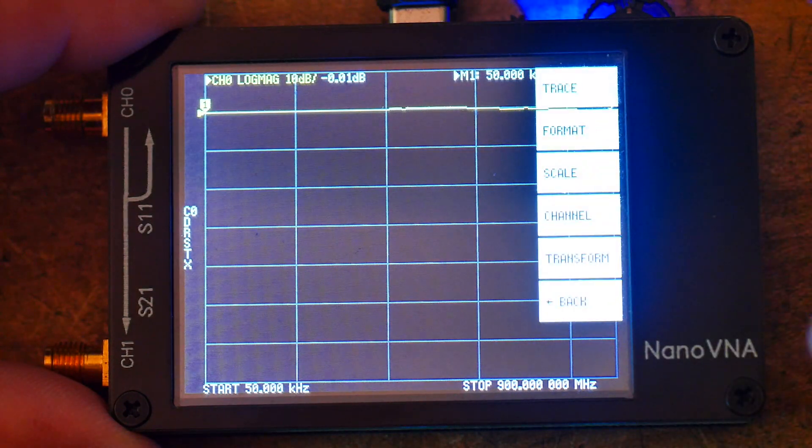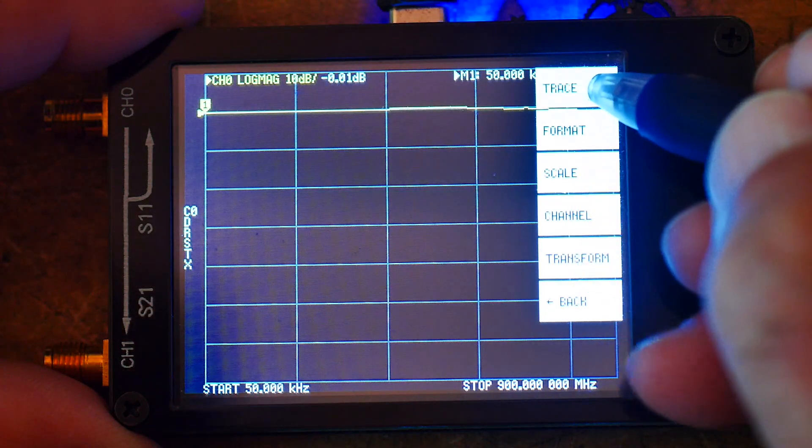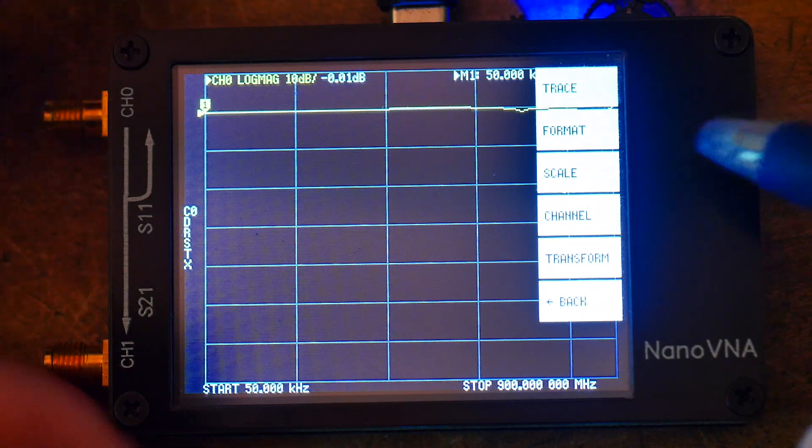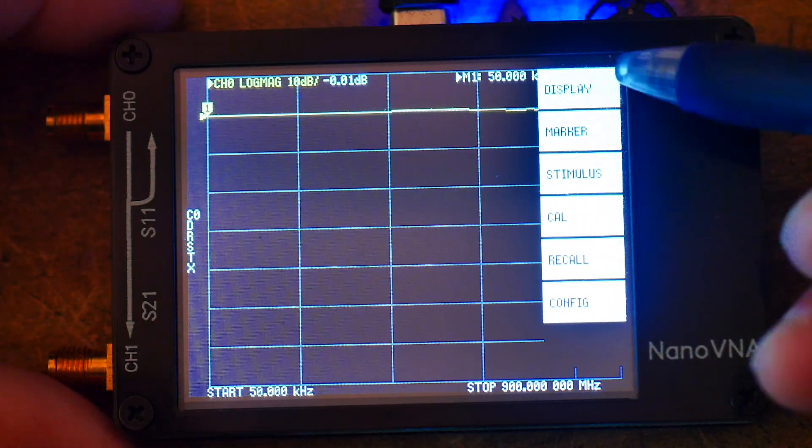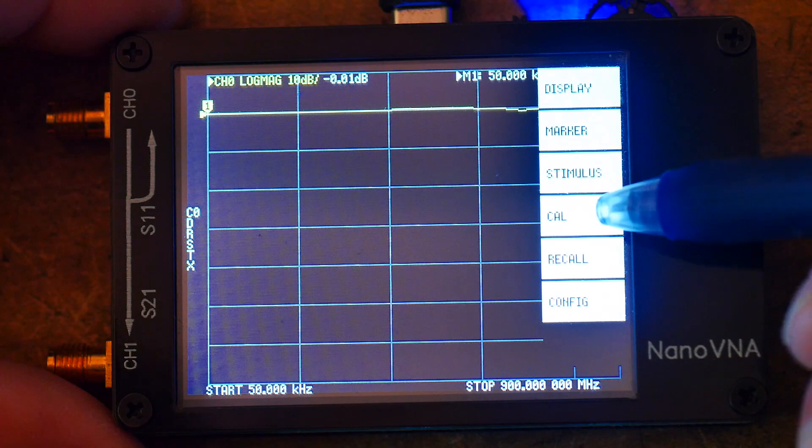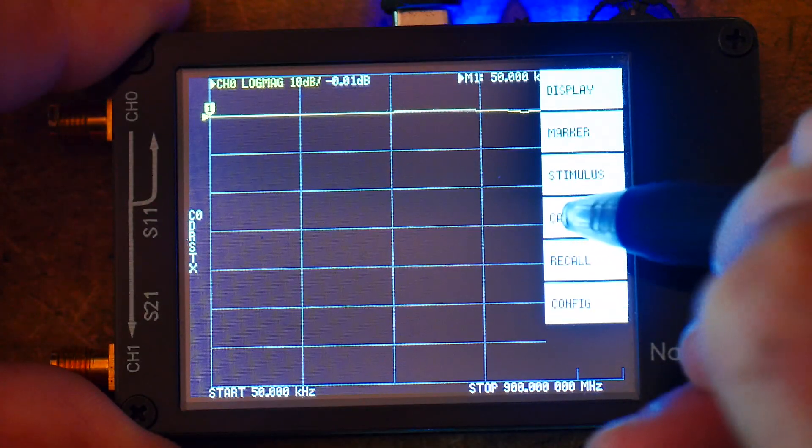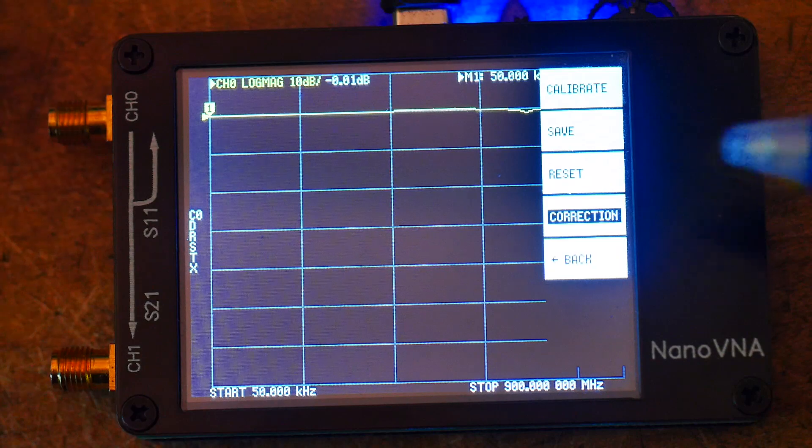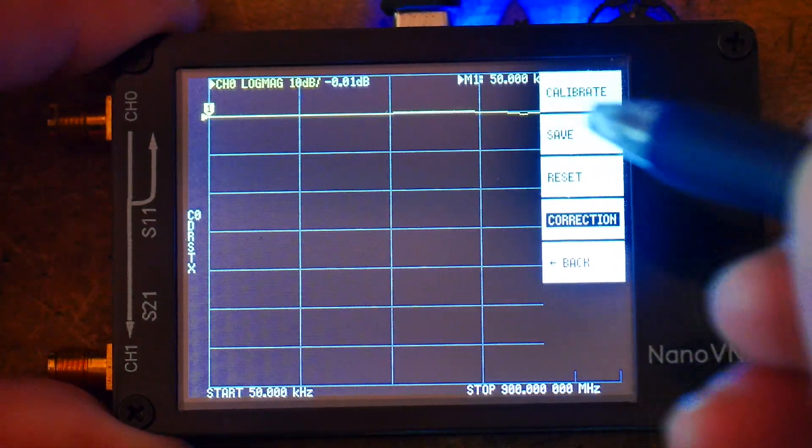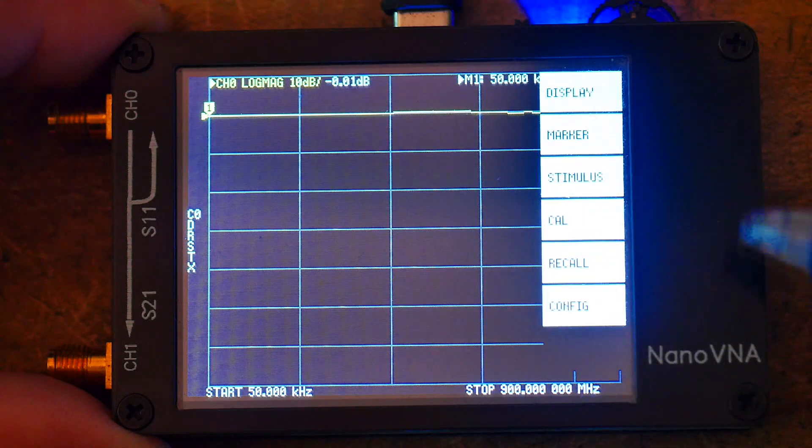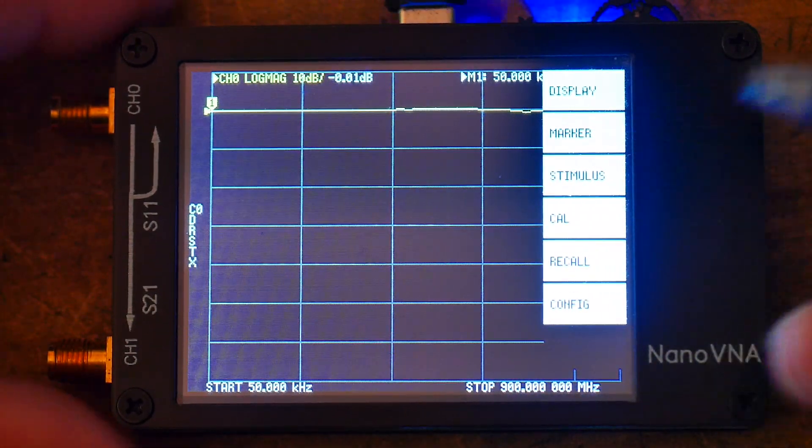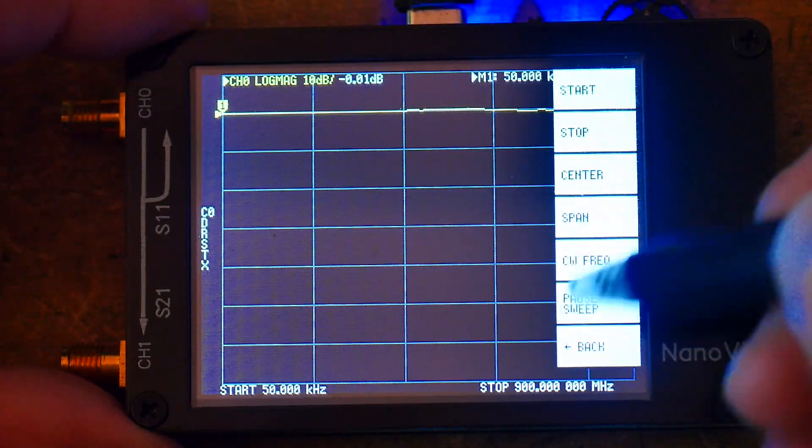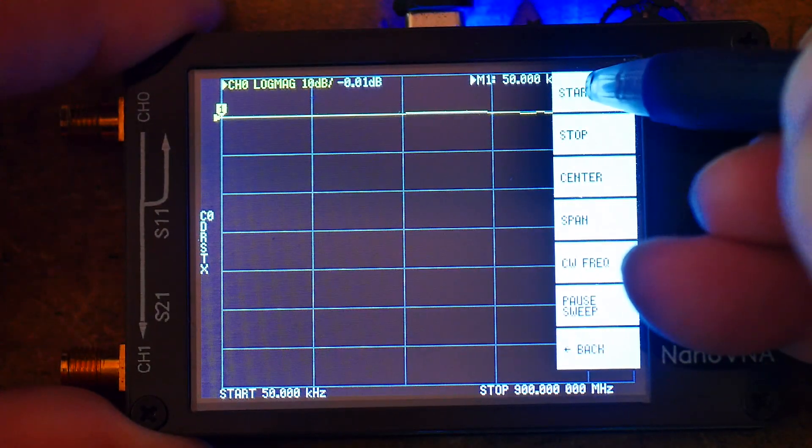Again, we're going to click the upper right. We want to hit calibrate. So do we see it? Trace, format, scale, channel, transform. I don't see it. So we'll click back. Oh, wait a minute. Now I get a different menu. Display, marker, stimulus, CAL. That's what we want. We're going to hit calibrate. Now before we do that, though, we have to set up the frequency range that we want to operate on. So let's go back and we're going to hit stimulus. Stimulus just means what frequencies we're going to use. So we hit stimulus. There we go. We'll see start and stop. Forget everything else. We're just going to use start and stop.